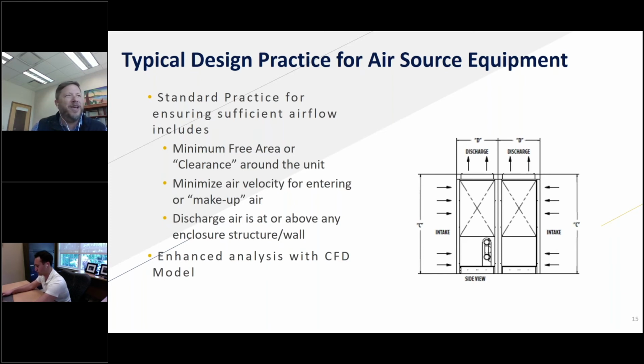And this happens all the time in the city where we want to hide the equipment, right? Whether it's for aesthetics or for sound, we end up putting an enclosure around the unit. In those cases, the best way to make sure we don't have air recirculation is that wherever the air discharge is, whether that's the top of the unit or some ducting off the top of the unit, we get that to the same level as the enclosure structure wall, or slightly above. That would give us our best chance to ensure we don't have air recirculation. Those are the kinds of practices that we use.